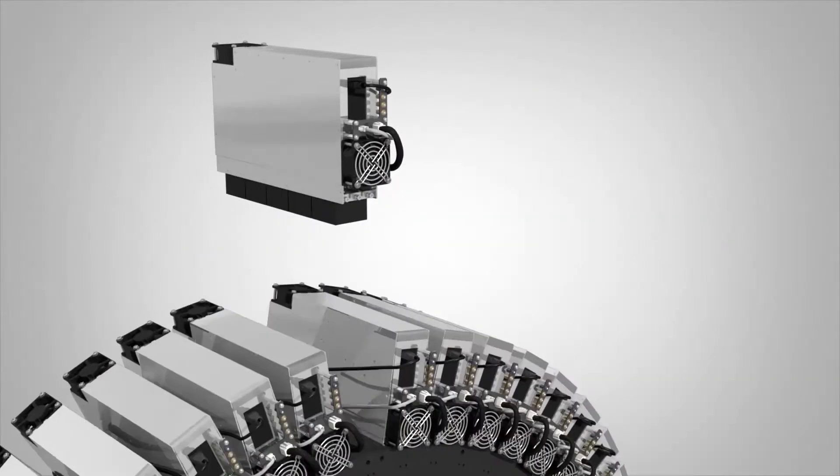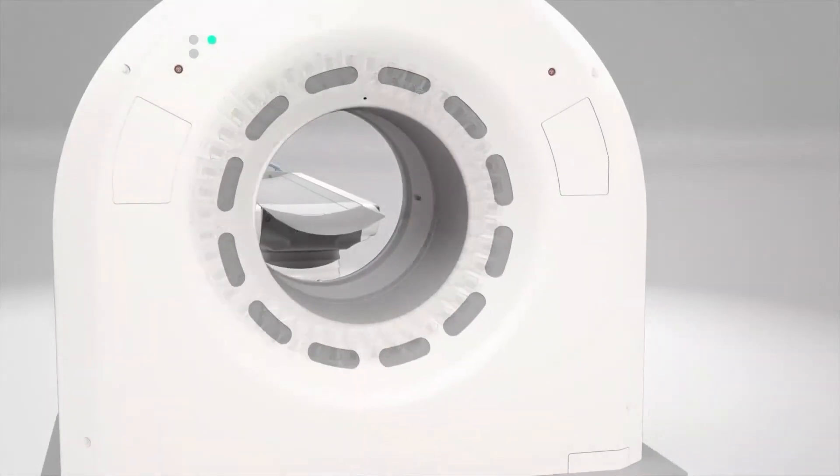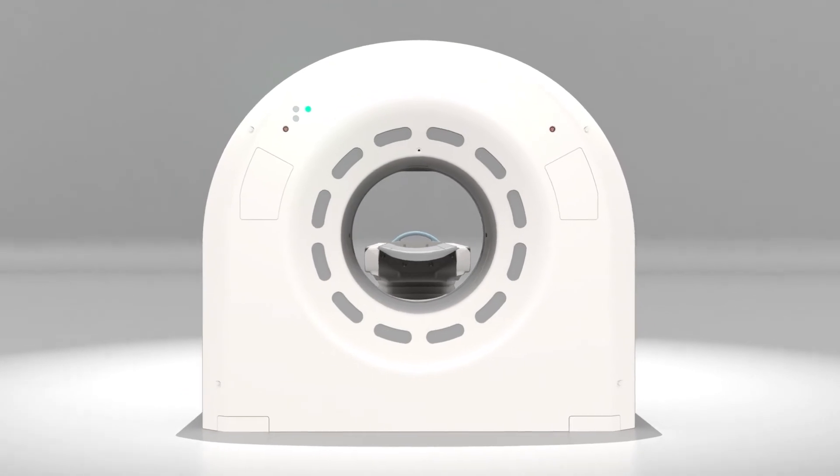In the past, digital PET-CT has only offered water-cooled solutions, which have been associated with costly room renovations, new construction, inconsistent chiller performance and high service costs. Canon has now unlocked the true potential of digital PET-CT. As the world's first 100% air-cooled digital PET-CT system, the Cartesion Prime alleviates many costs, risks and complexities associated with water-coolers.